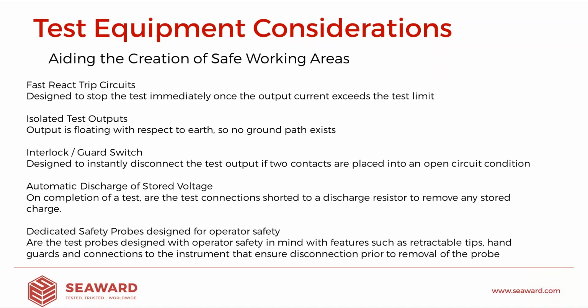What we don't necessarily want is that we hit a condition where the fail point is hit. So let's say our tester has delivered more than 5 milliamps on our pass limit. And what happens is the test continues on until the end of time of the test, and then reports back that there is a failure. What we want to happen is, as soon as that condition is met, the tester will stop the test instantly and alert the operator that the fail condition is met. So we're looking for fast react trip circuits.